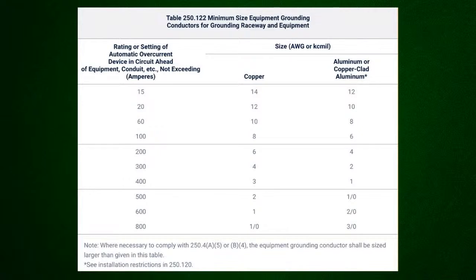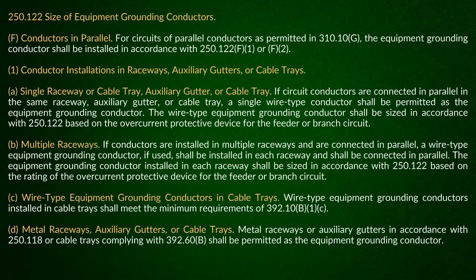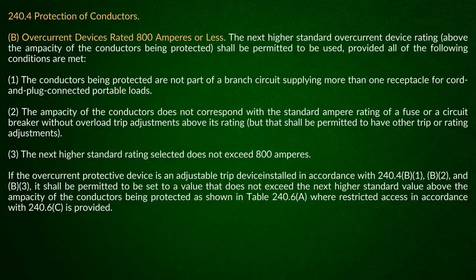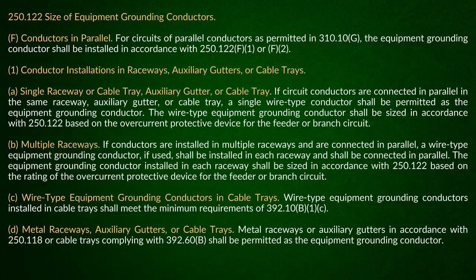Okay? Now, I want to go back just right here. When you come over and you're looking at the size of equipment grounding conductors, if you go down to 250.122(F), it talks about your conductors in parallel. And they tell you, what if I do it in multiple raceways? It doesn't really matter how you're going about it, but you're still going to do it based on what?